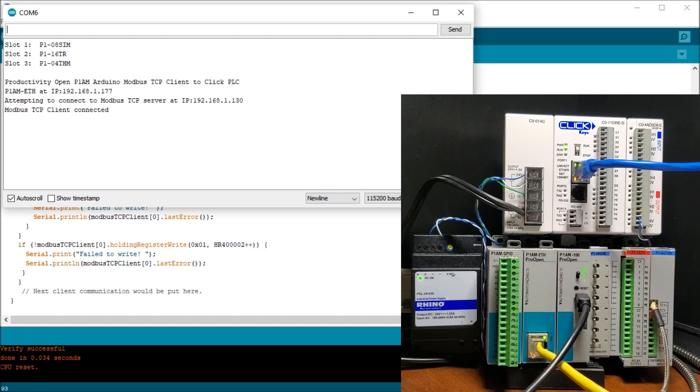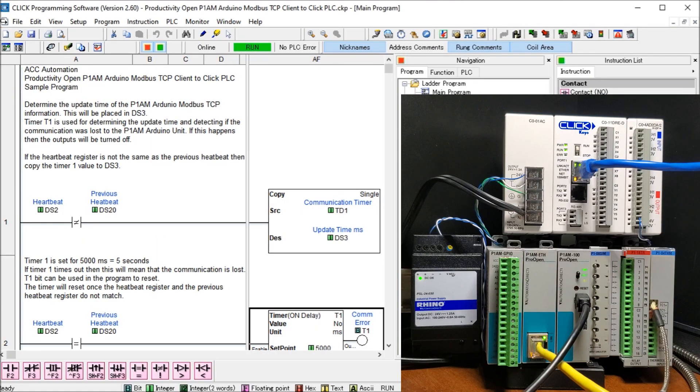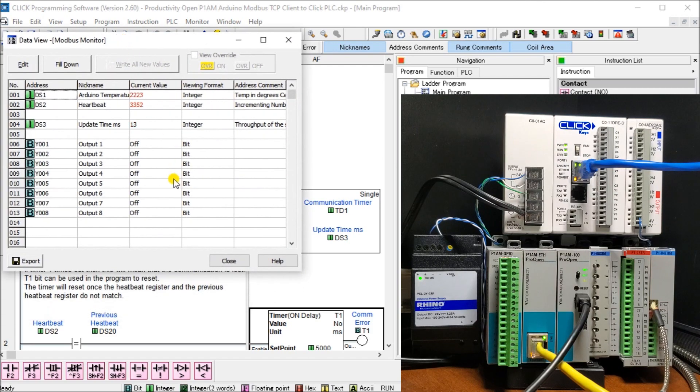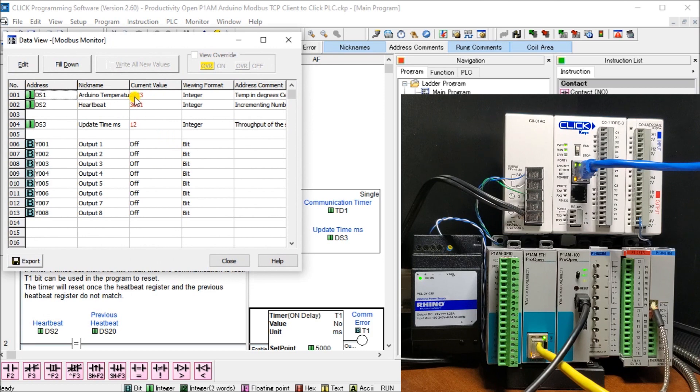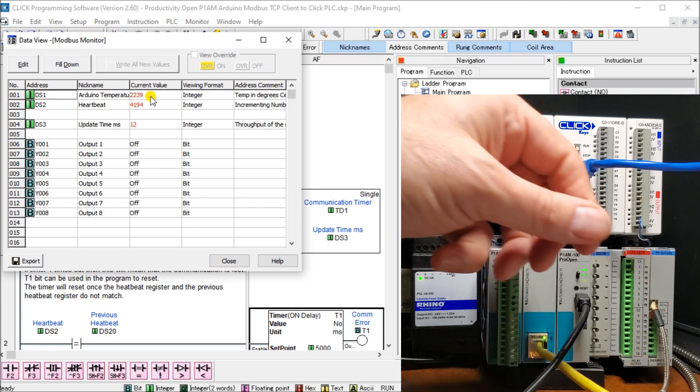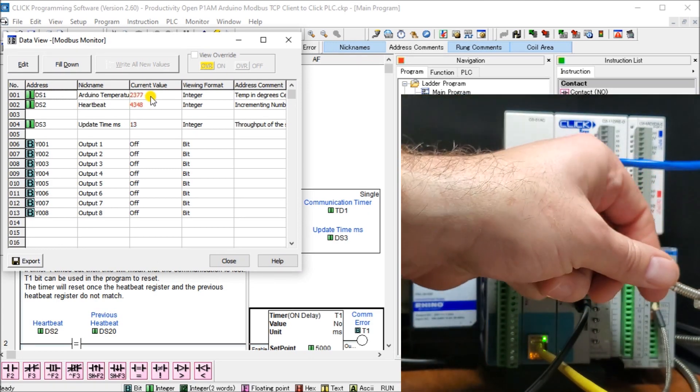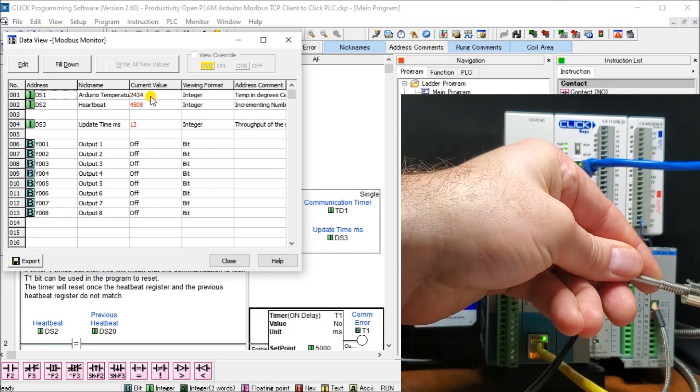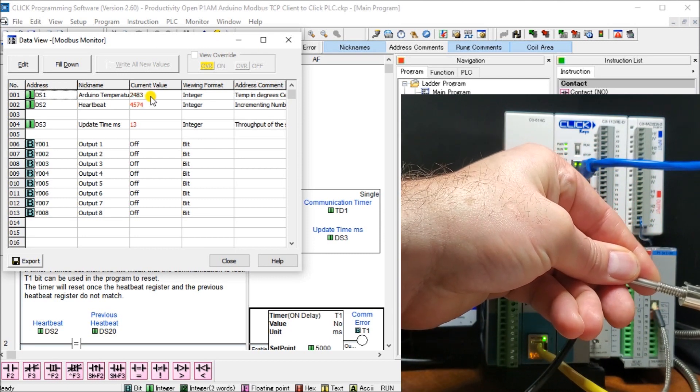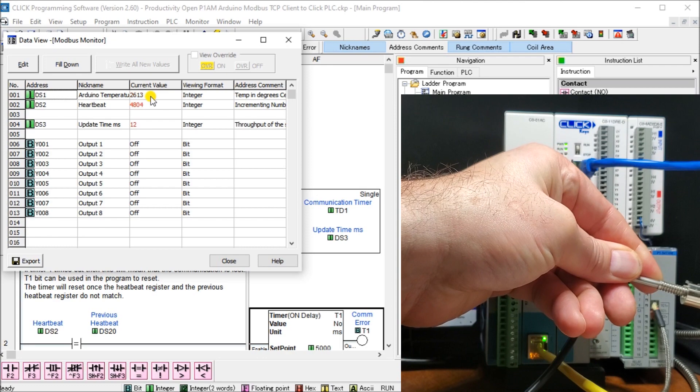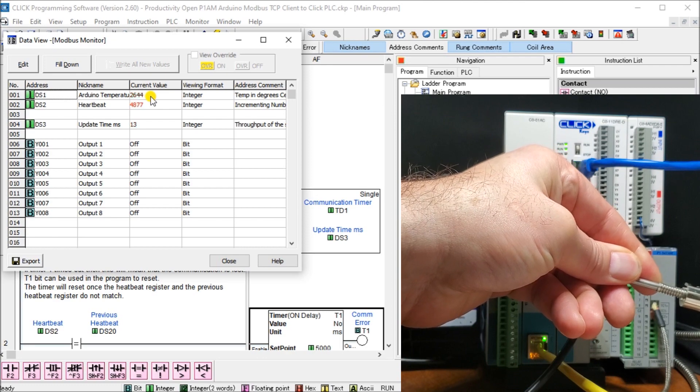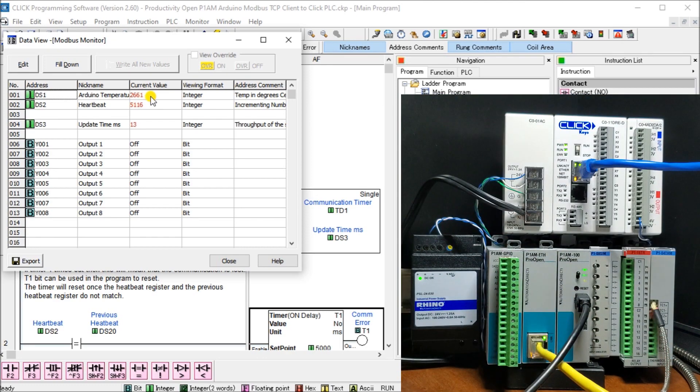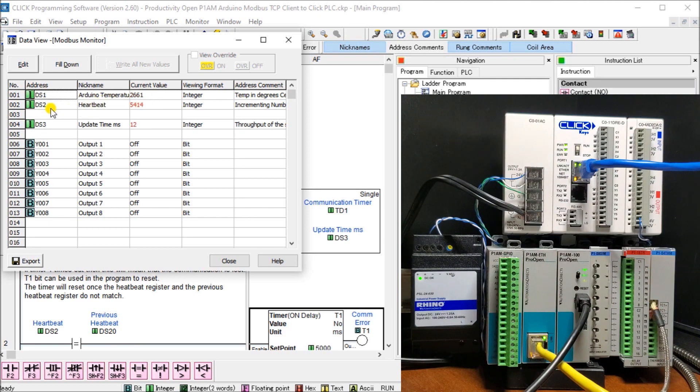So now let's look back at our Click PLC program. And let's just monitor using data view, our Modbus information. There we go. So you can see here, we have 22.23 degrees Celsius. And what we can do is just to make sure we're testing that out okay. We can hold on to this probe. And when we do, that number then starts increasing, as you can see here. So we're now at 26. So that seems to be working fine. And we're getting that information in.